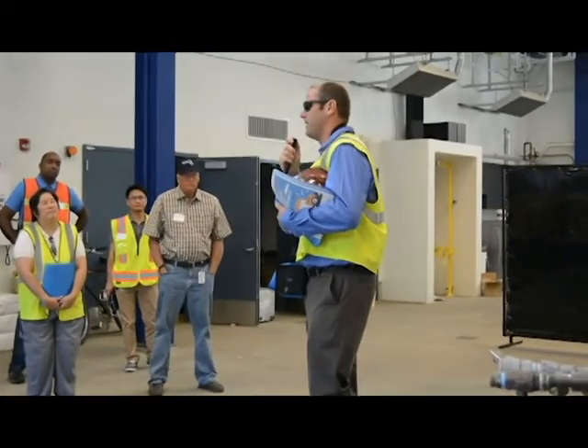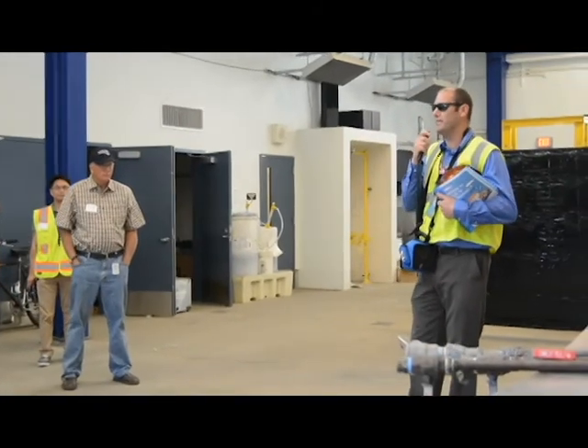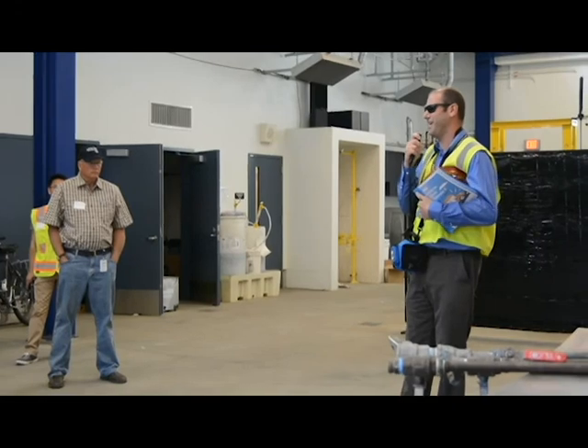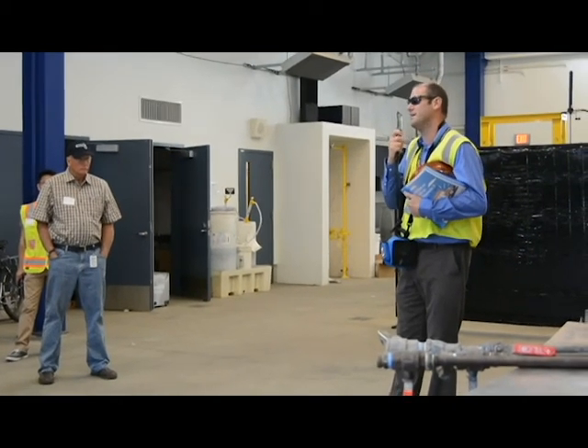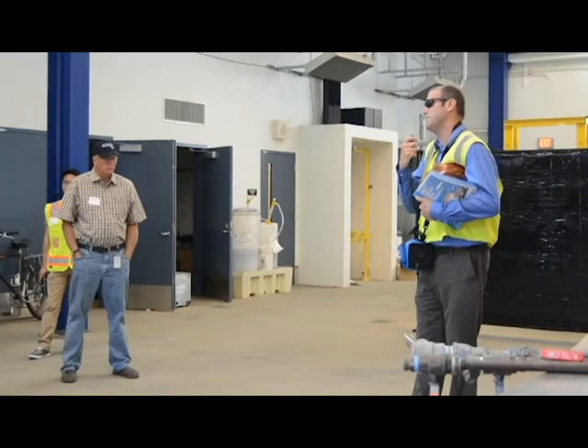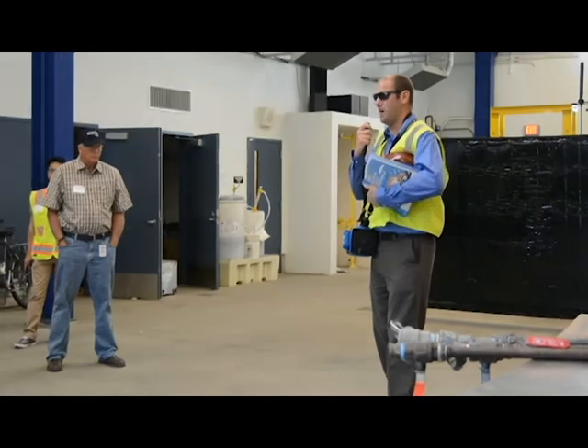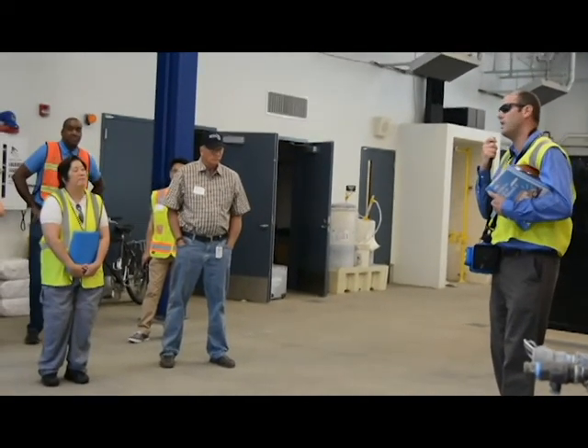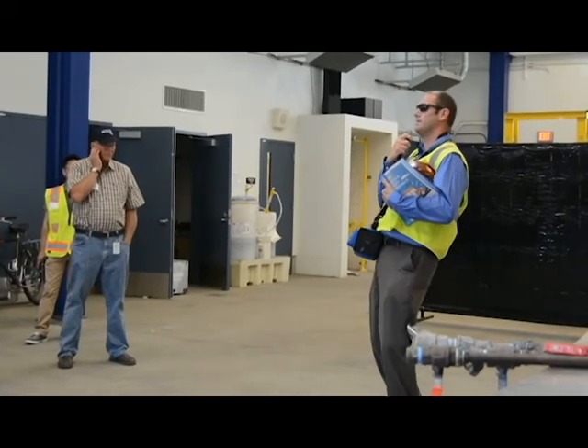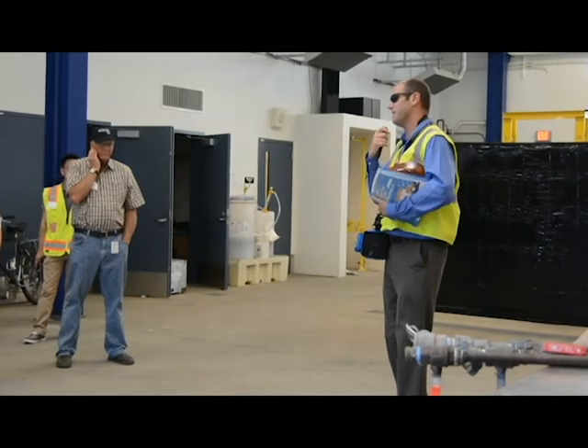Airplanes do not like carrying water around, right? That costs money. So they carry that blue fluid that is actually toxic to our fish and our bioassay and everything else. So we've got to be very careful. We'll be putting color monitoring in our new plants, because if United Airlines, which is the dominant airline, gets their dosing wrong, if something happens with the little orifice plate, they can overdose their planes. We get that blue liquid here, it wipes out everything. It kills our bacteria in our process. So again, we're very unique.